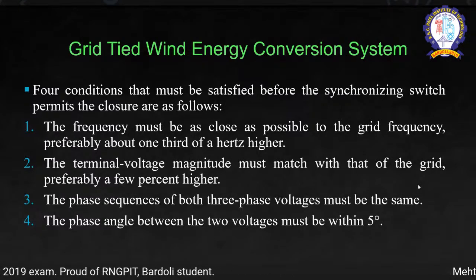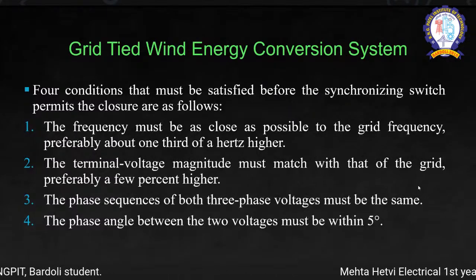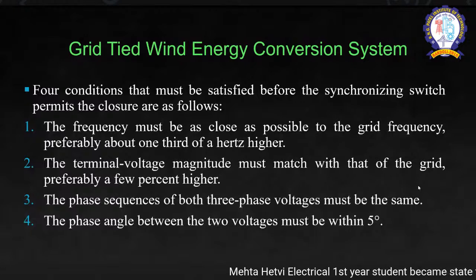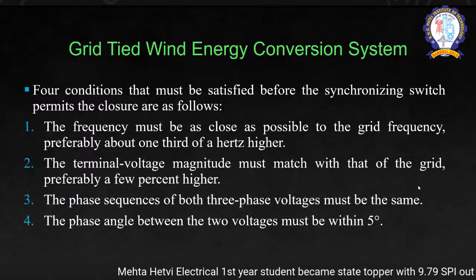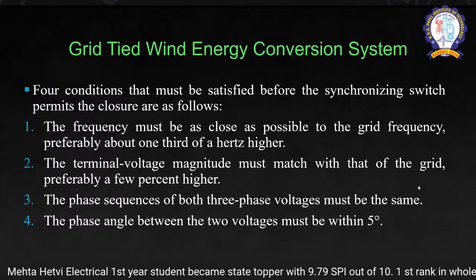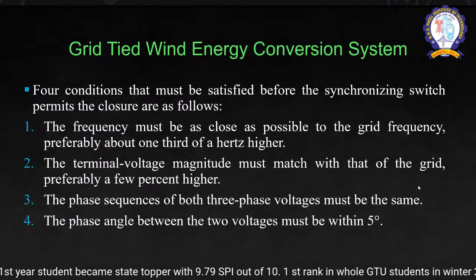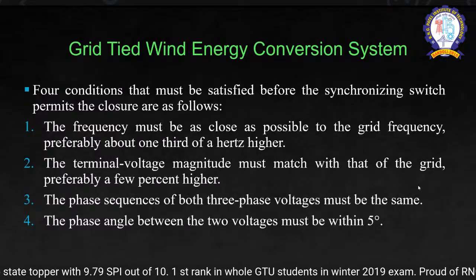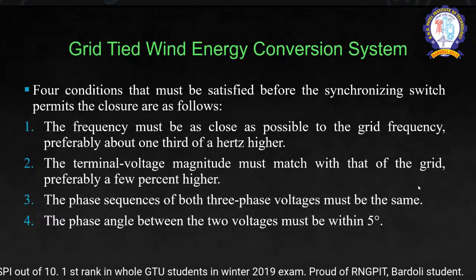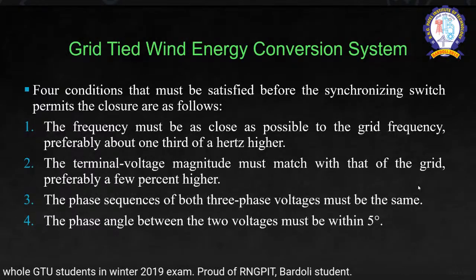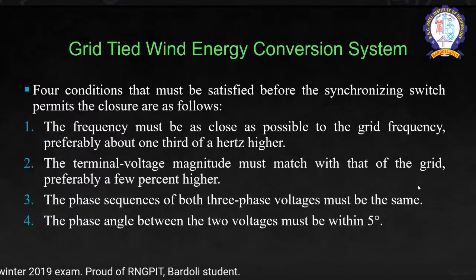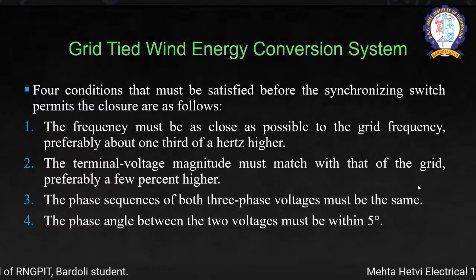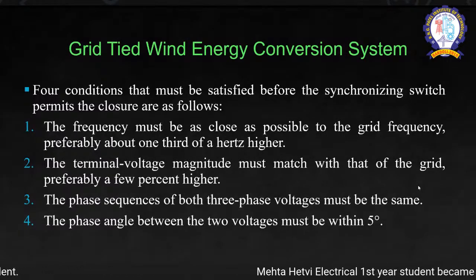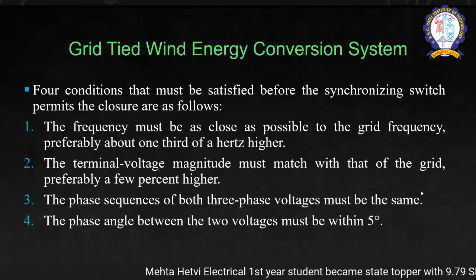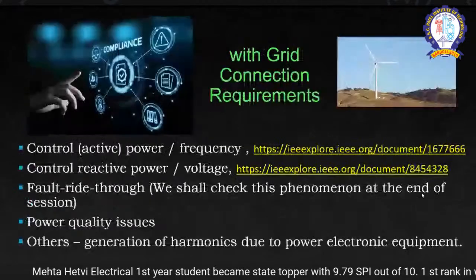The phase sequence is one of the major aspects: the three phase voltages must have the same phase sequence. So if you connect the transformer with that, it must be of the same phase sequence, and that is a preliminary rule for connecting transformers in parallel also. And the phase angle between the two voltages must be within 5 degrees, so we can allow this wind turbine to be integrated with the grid.